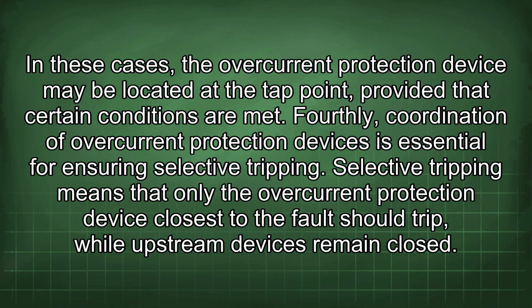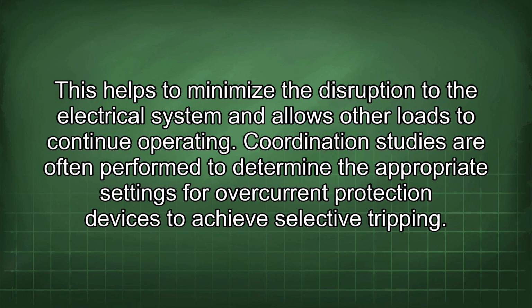Fourthly, coordination of overcurrent protection devices is essential for ensuring selective tripping. Selective tripping means that only the overcurrent protection device closest to the fault should trip, while upstream devices remain closed. This helps to minimize the disruption to the electrical system and allows other loads to continue operating. Coordination studies are often performed to determine the appropriate settings for overcurrent protection devices to achieve selective tripping.